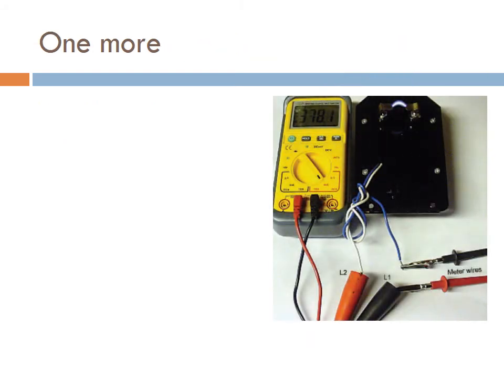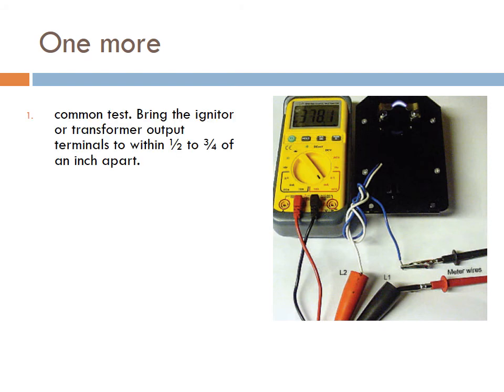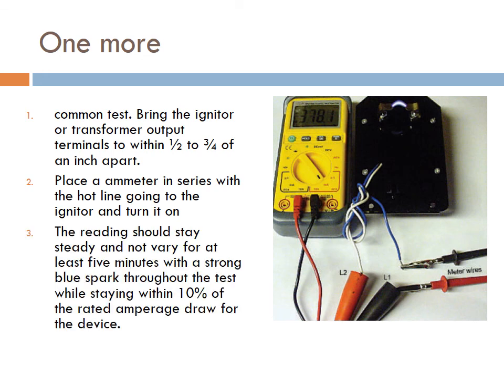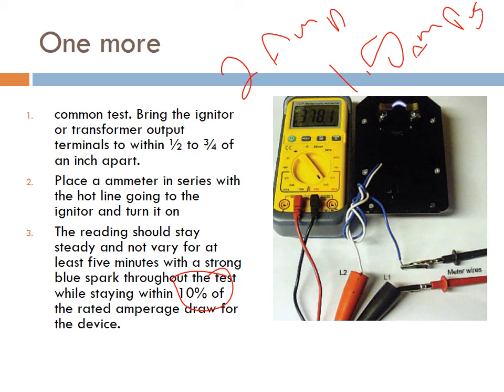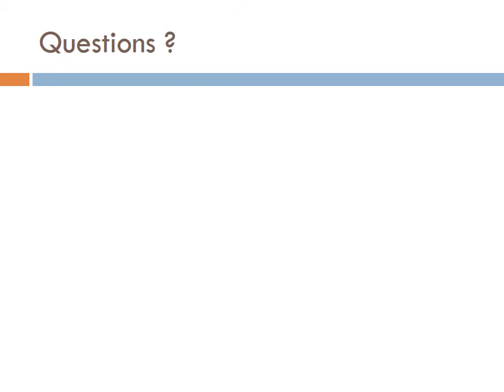Another way to do it, which I find more practical, is to put an ammeter in series, or you can use a clip-on meter, put it in a loop once or twice, turn it on, leave it on, and check for amperage drop. So place an ammeter in series and check for amperage drop. It should stay within 10%. If we start with, for example, 2 amps, and after 10 minutes it became 1.5 amps, that's a 25% drop, which is not really good. That means the transformer is bad. So that's another way to test a transformer.